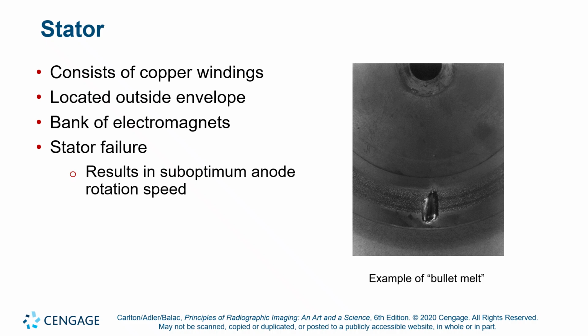Now, a stationary anode is designed to take bombardments all in one location, and so you're not supposed to get a bullet melt. You can on a stationary anode if you overload it and ignore the heating chart. If it's a really old one that doesn't lock you out from the exposure, then you could effectively put a big melting hole burning through your stationary anode. But typically this manifests in a rotating anode that failed to rotate.